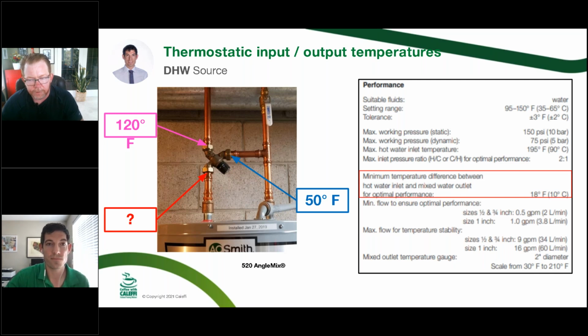Yeah, I think that's one of the things that gets overlooked quite a bit. You look at that and go, I'm putting this device in as an anti-scald, as a protection device. Well, the reality is, yeah, we want to make sure we don't have any issues with health and safety, but the mixing valve is going to boost that output. I think the other thing that is important to note, what Max said, is that in the case of this particular valve, it's looking for 18 degrees difference. It's not every valve. Not every valve is the same. Just as we're about to talk about the Legio mix, and Patrick has a question on the minimum on the Legio, which we'll talk about, it's not the same as using this product. So it's a little bit different.